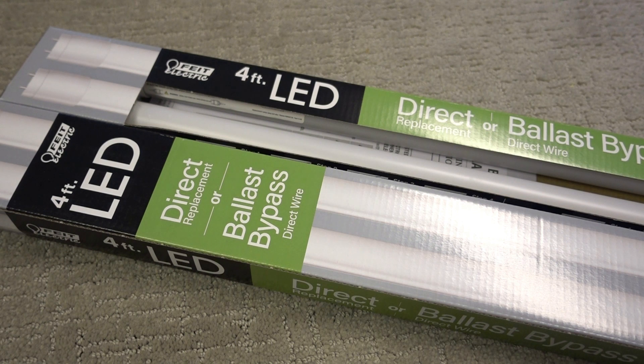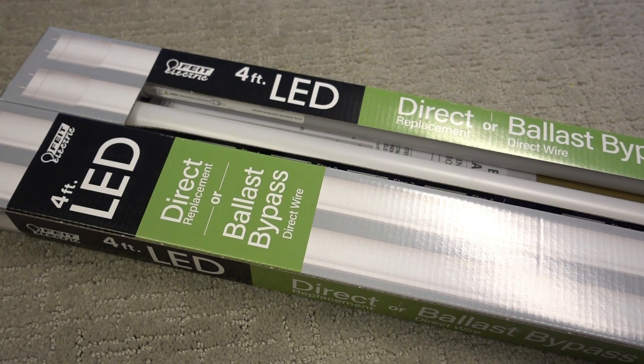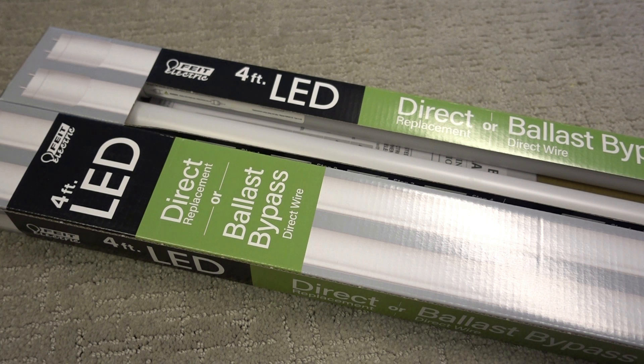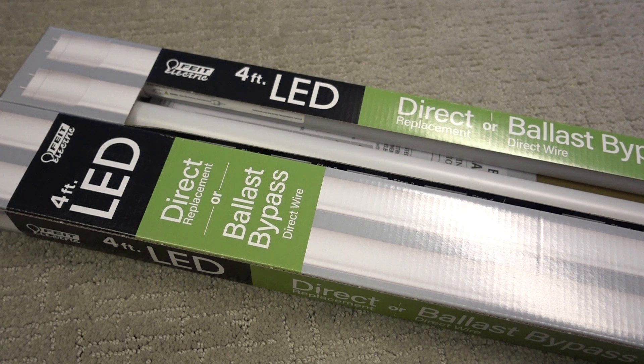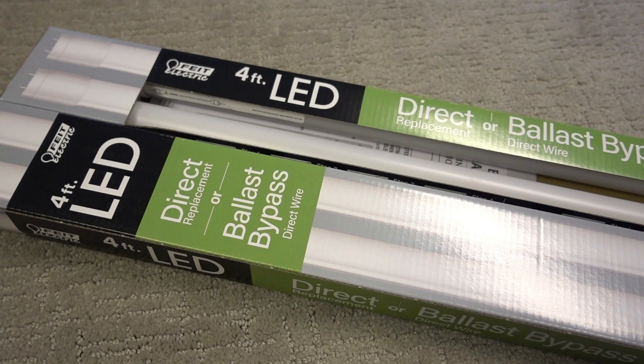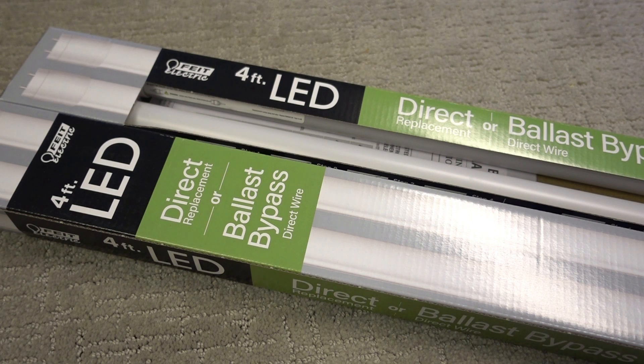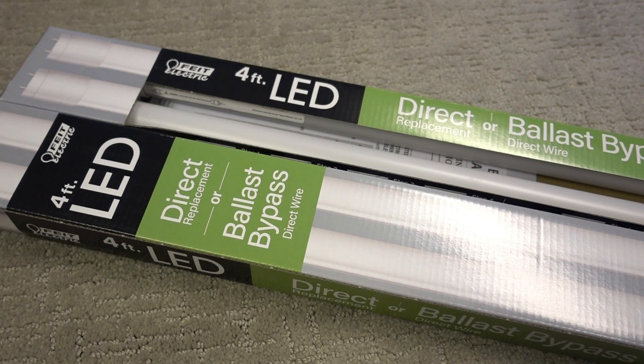If you follow my channel, you know I just did a replacement on my fluorescent lights in my shop. I tried to use the plug-and-play tubes, and that didn't work out. I brought those in here in the den where I'm replacing the fluorescent tubes. That didn't work either, and the reason for that was they were not compatible with the ballast. Even though these lights in here are a different brand, they weren't compatible either, but just for the heck of it, I'm going to try it.